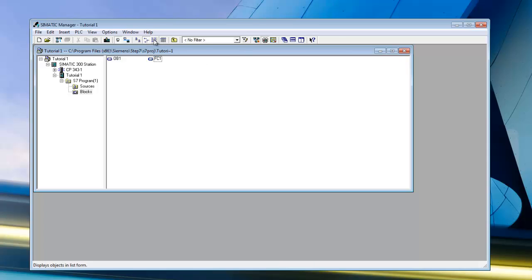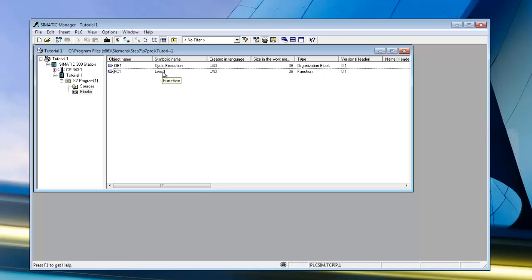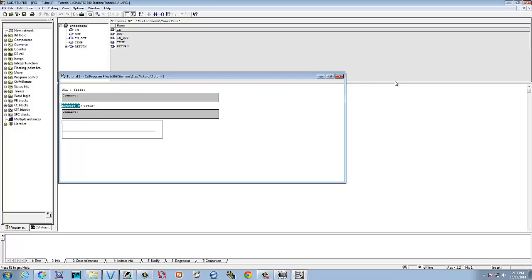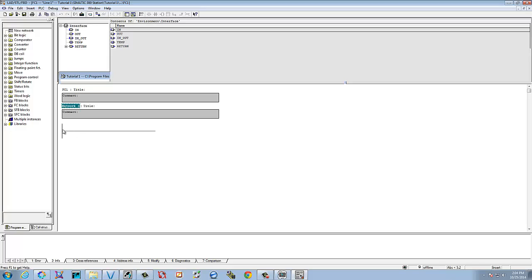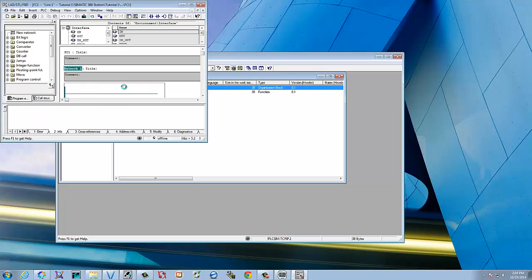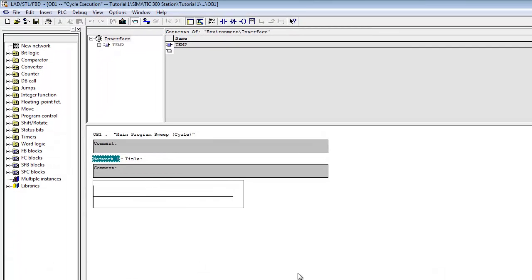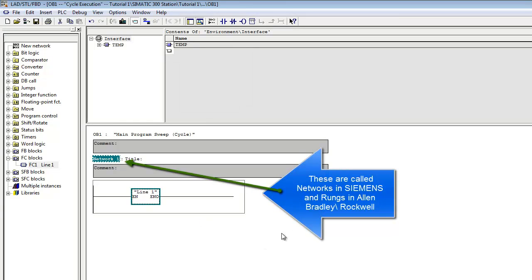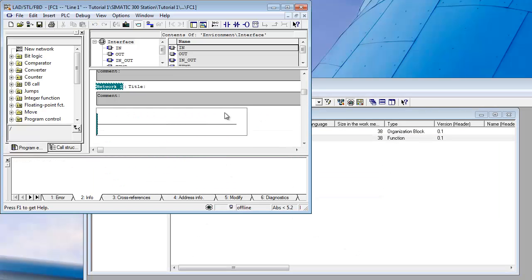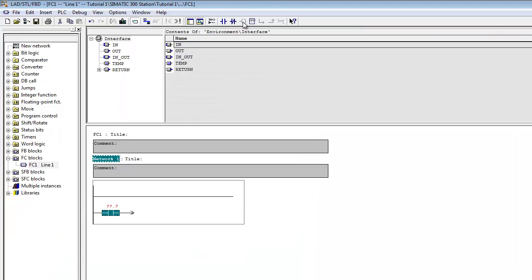We'll change our view to list. Right here is your symbolic name — it's set for Line One. Open it up and you have the start of your function block. We'll go back to our Organizational Block because we need to call Line One from there. Over here in the FC list, there's Line One — drag it out and drop it on the first rung. Now when it scans the Organizational Block, the first thing it does is scan your function block. We can now go back and open up that function block and put in a simple routine.